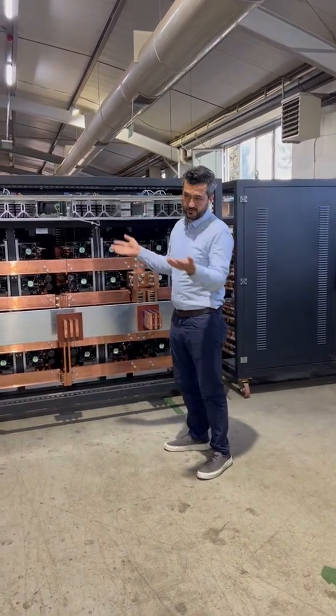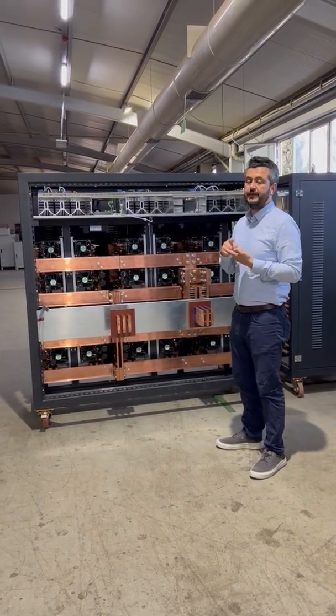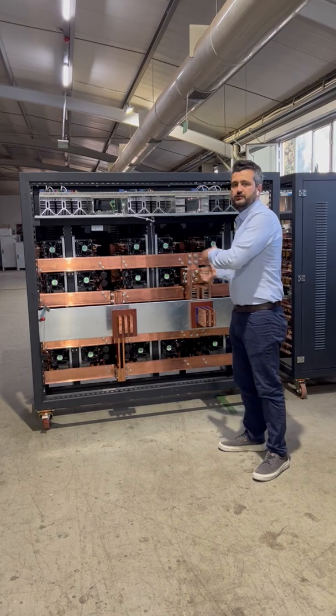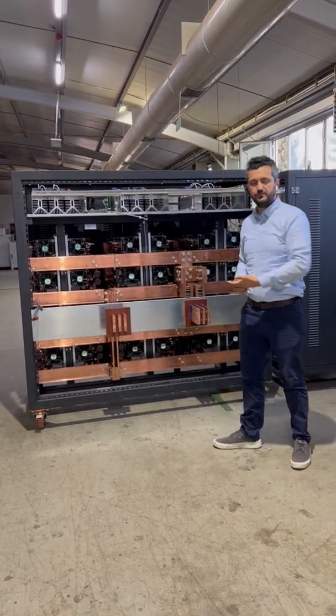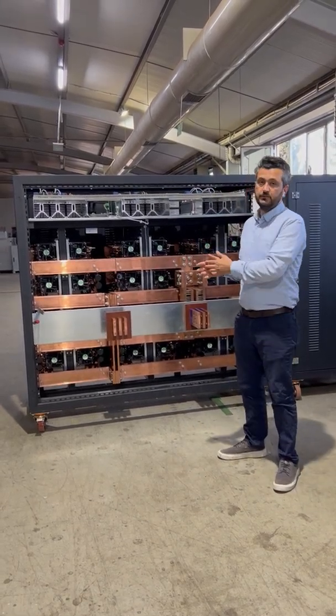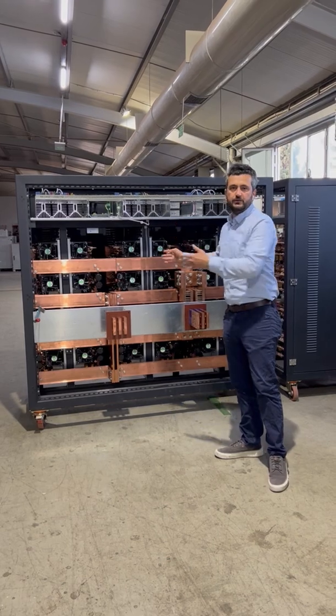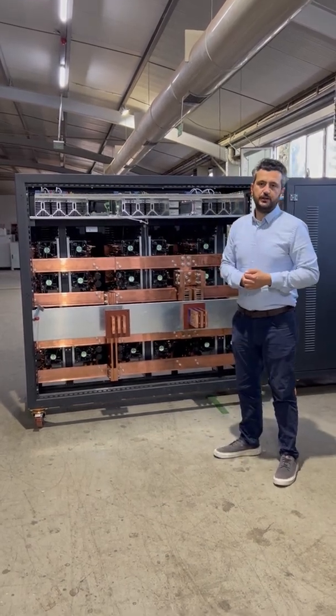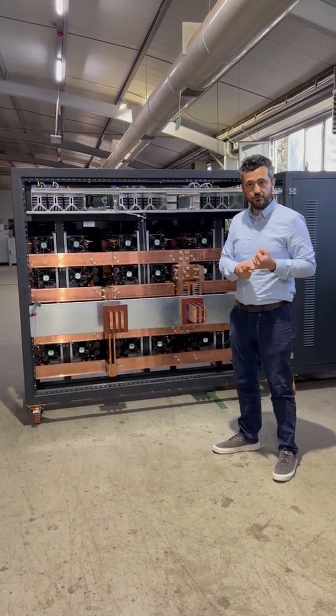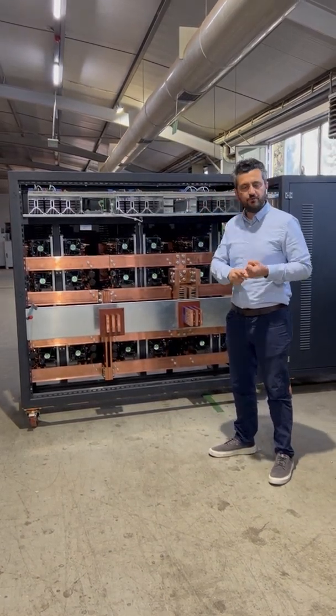While you are using the machine, because it's a dirty area like a factory floor, you have to make sure you have good, cold, fresh air coming in and less dust and less chemicals reaching the machine, to let your machine work for more years. We give 2 years warranty, but some clients do not care about the electrical room conditions, which can affect the machine and any electronic components that run it. So while you are using a rectifier, we suggest switch mode solutions.